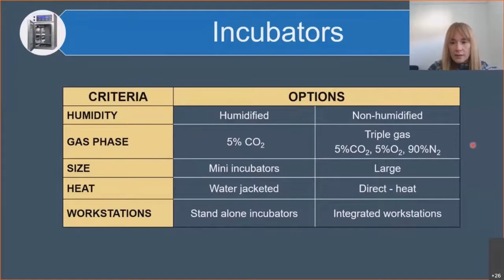In this slide, we can see the difference between large and benchtop incubators. Large incubators have several advantages as they can be used to equilibrate large bottles of media, and they allow independent probes to be installed. They provide extra space. However, we have to remember that every time we open the door, the bigger the incubator, the slower the recovery rate, so it takes more time to go back to the required conditions.